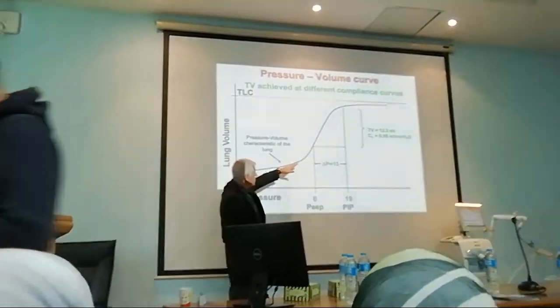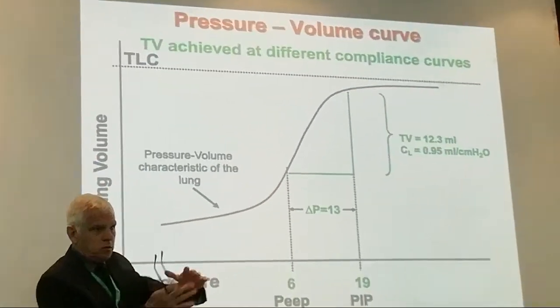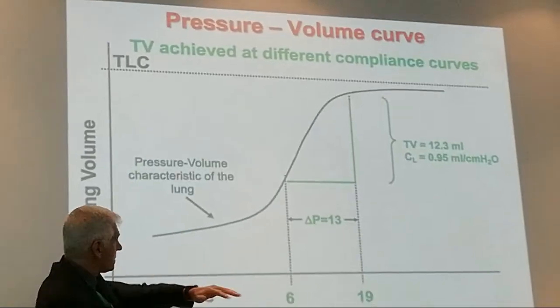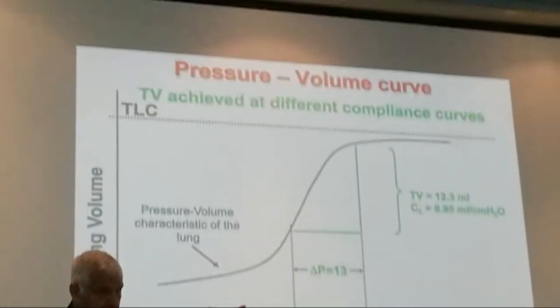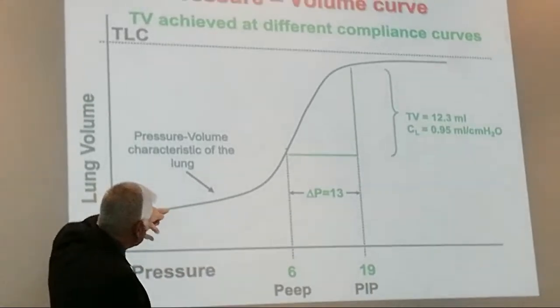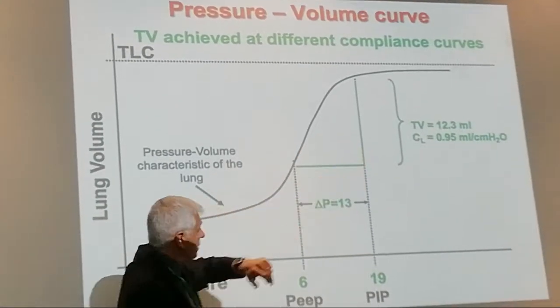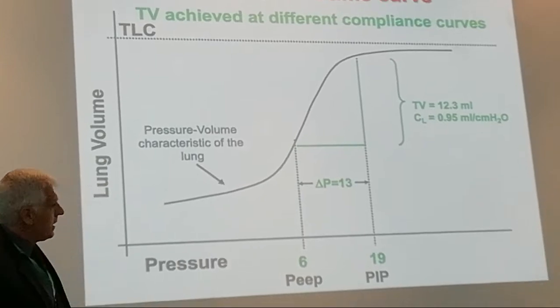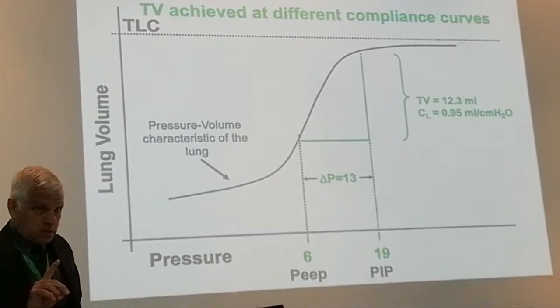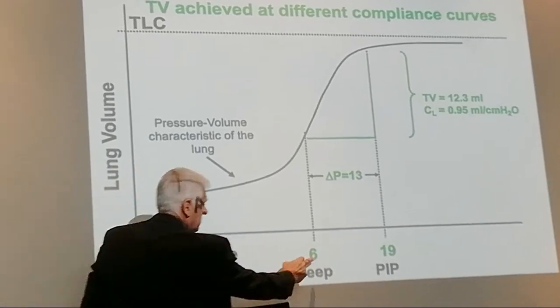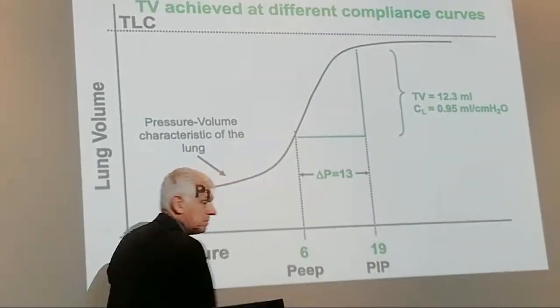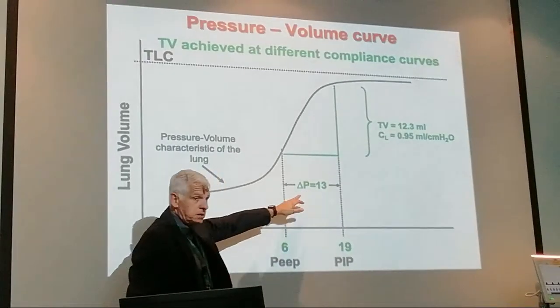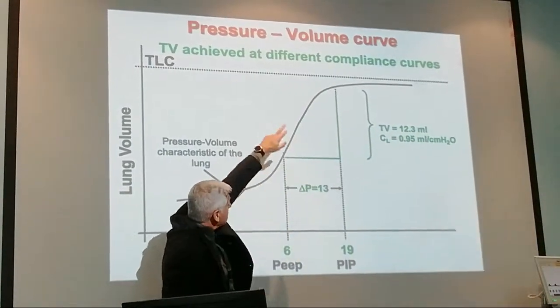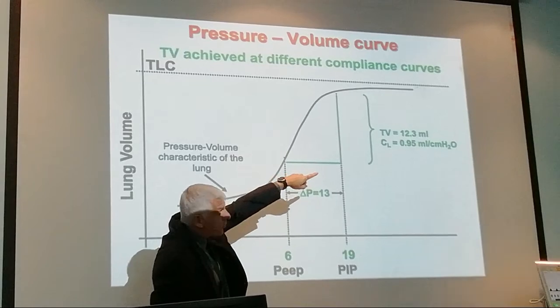So, here we have an example. This is the static pressure-volume curve. You don't have two limbs because it's not dynamic, it's static, so this is kind of the average of the inspiratory and expiratory. This is a normal compliance curve. This baby is being ventilated with pressure, with a PEEP of 6 and a PIP of 19, so your delta P is 13. The volume that you get with that pressure is 12.3.